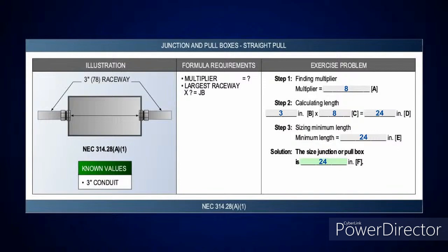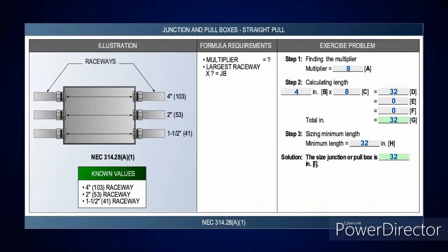This is where you do your straight and angle pulls. This is probably the most simple calculation in the code. If you go over and look at NEC 314.28 A1 and A2 — A1 deals with straight pulls. You should know this off the top of your head: the multiplier for a straight pull is 8, and for an angle or U-pull the multiplier is 6. For a straight pull with a single 3-inch raceway, take 3 inches times 8 — the minimum length across that box has to be at least 24 inches.